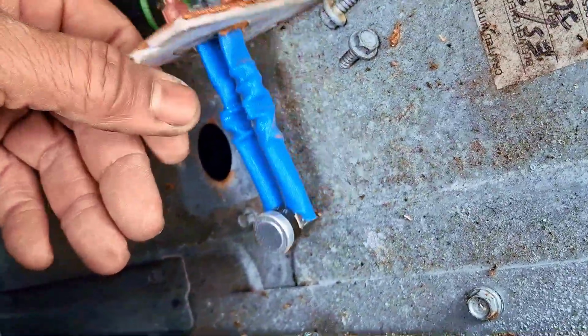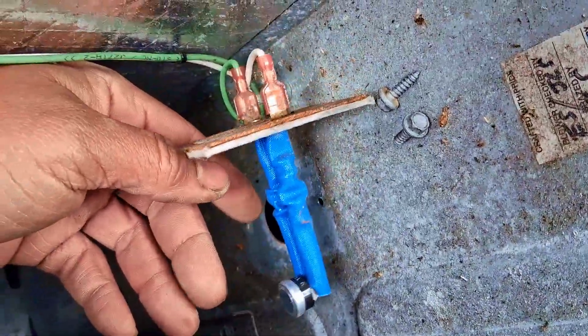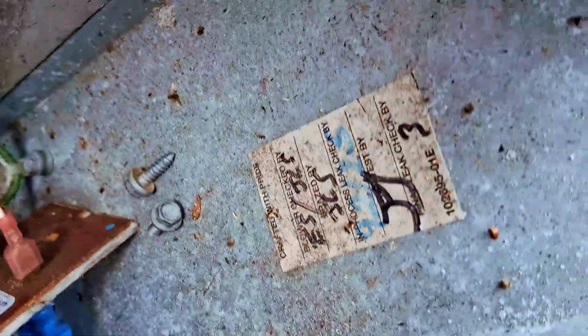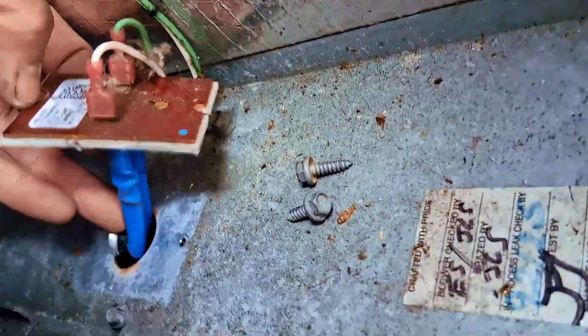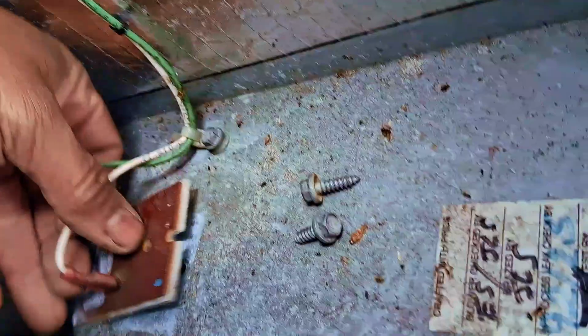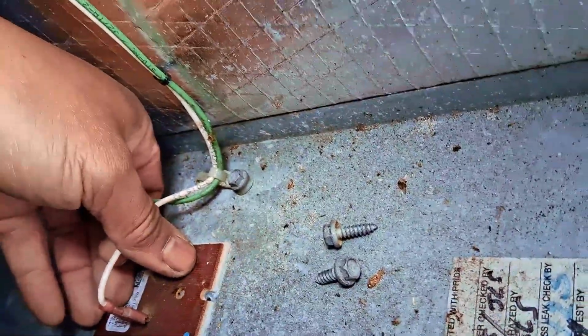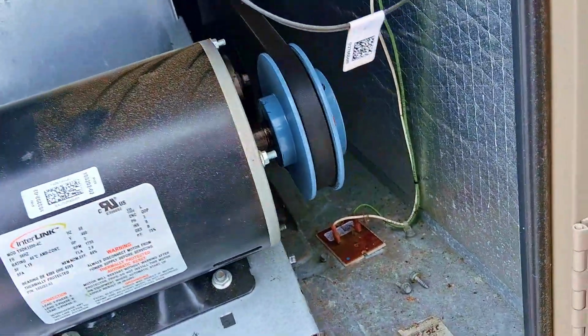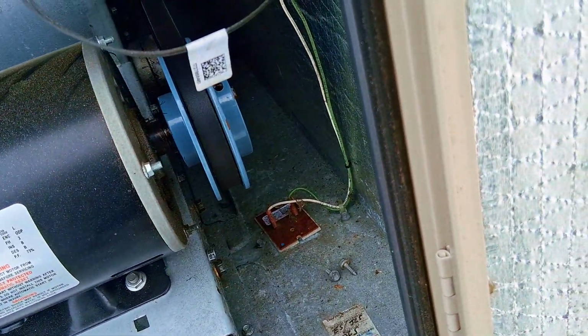Alright, so I'll show you guys the high limit, how it looks. See here, it sticks down in there, and that's it right there. It's the high limit. It looks pretty good, it doesn't look bad at all, actually. That goes down in here and reads the temperature in the heat exchanger section. The heat exchanger section gets super hot, which lets you know it's an issue, and it'll turn the unit off.